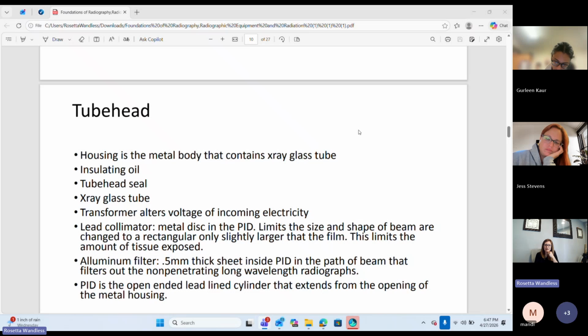That is what we were talking about the other day with Wilhelm Röntgen, who invented that. It's a glass tube about 6 inches long and about an inch wide. We're going to get a little more into what that glass tube is shortly, but I just want to describe that. That is the heart and soul of the whole X-ray machine, no matter what type of machine it is. That is where we're going to harness our energy and fundamentally make that electromagnetic radiation.